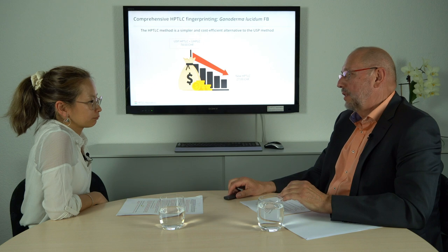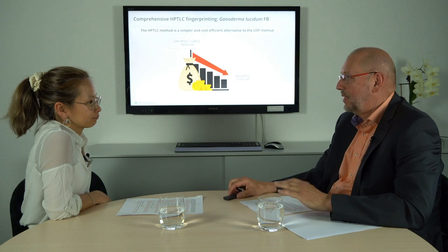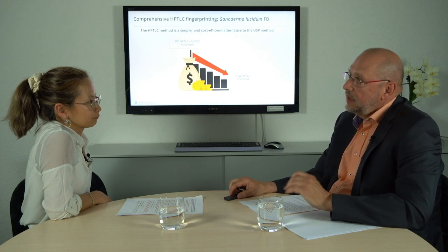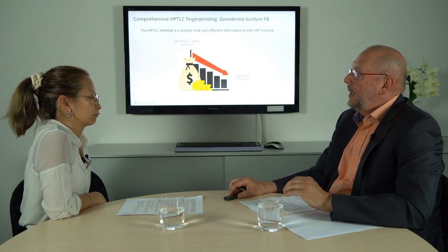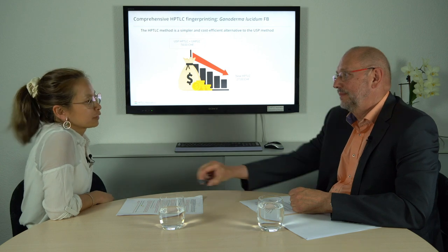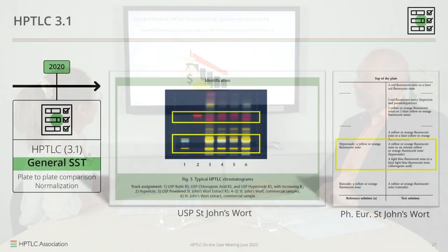There is still the question of suitability of instruments and methods. To be sure the method and instrument are working properly, use of a system suitability test, or SST, would be needed. In HPTLC, most regulations qualify the analysis based on the resolution between two zones and the fingerprint pattern. For example, in the USP and pharmacopoeia monograph for St. John's Wort, resolution between hyperoside and chlorogenic acid is requested.